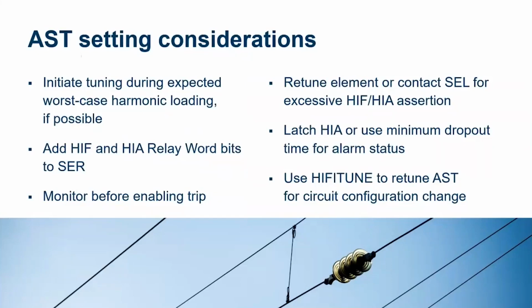So we definitely recommend applying this in locations where you have communication or easy access to the device that you're applying AST in, and put those high impedance fault bits and alarm bits into your SER. Bring back those over DNP so that you can see how often they're asserting and if there are any kind of patterns. And whenever you get those assertions, we definitely recommend downloading those high impedance fault event reports and taking a look. And we're more than happy to take a look at those to see what's going on, to see if they look like potential nuisance trips, or if they look like they're actual high impedance fault events.